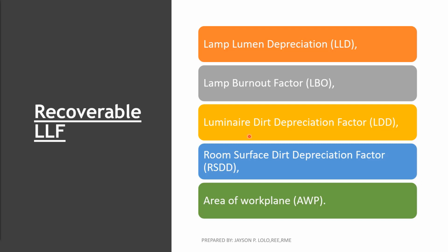Next one is the LDD, the Luminaire Dirt Depreciation. The Luminaire Dirt Depreciation factor depends on 3 aspects of the situation as follows. Number 1 is the amount and type of dirt in the environment. So let's have an example, a clean office environment compared to a dirty manufacturing facility. Okay, that is the number 1 aspect. The second aspect is the type of luminaire use. The third one is the expected cleaning cycle for the equipment. So, dira na siya. Muna siya mga factors.